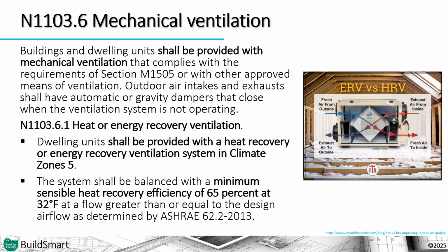BuildSmart does not only require balanced whole house controlled mechanical ventilation, but they also require using either an energy recovery ventilator or a heat recovery ventilator system. In addition, the ventilation system must have a minimum sensible heat recovery efficiency of 65% at 32 degrees and a fan efficacy of 1.2 CFM per watt or be Energy Star compliant. Balancing of the mechanical ventilation system is required and its flow rate must be determined by ASHRAE Standard 62.2-2013.